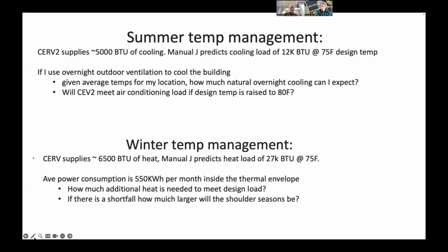What about winter management? The CERV will put in about 6,500 BTUs of heat. The Manual J predicts my total heat load is 27,000 BTU at a 75-degree design temp.